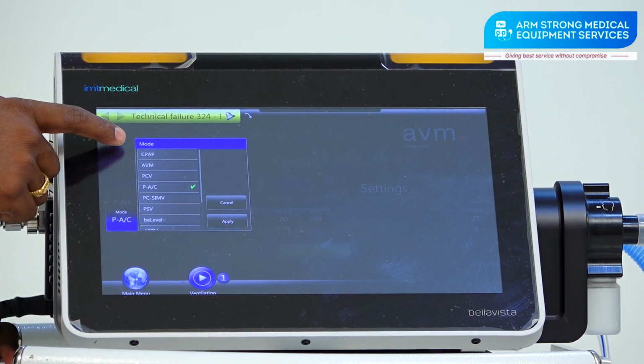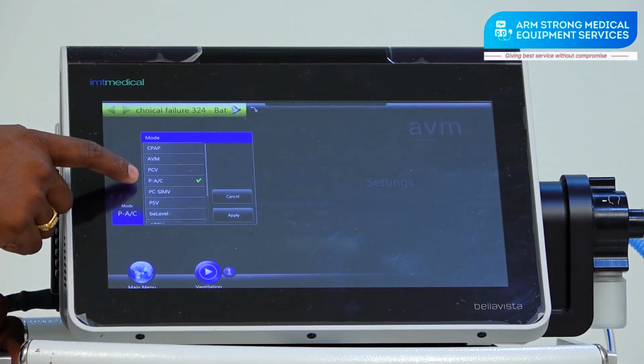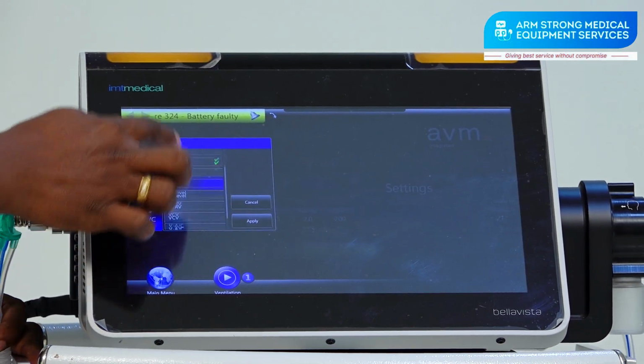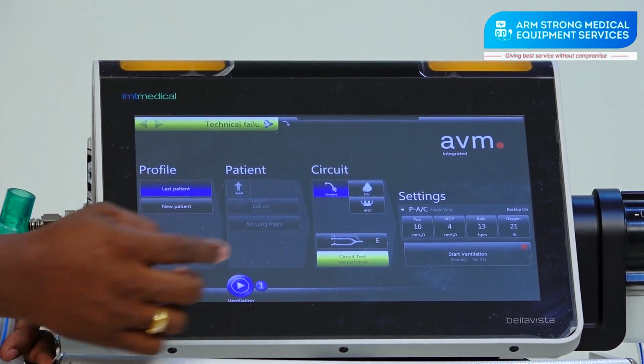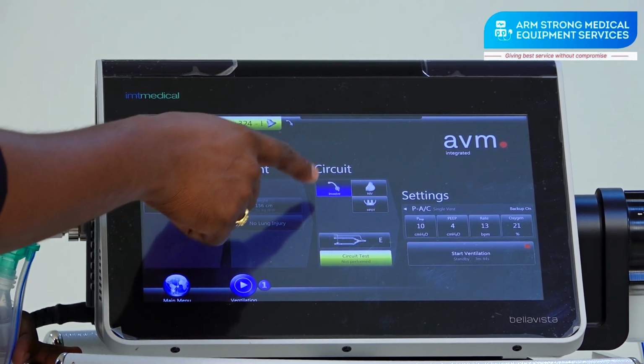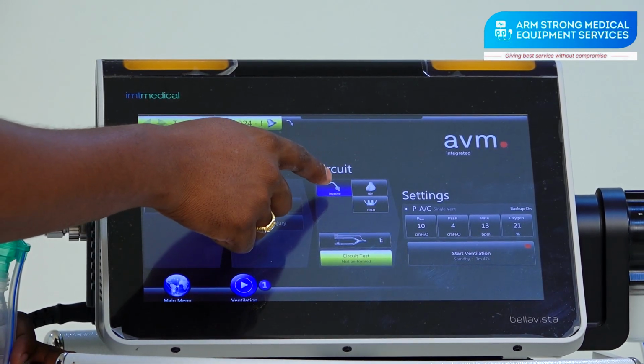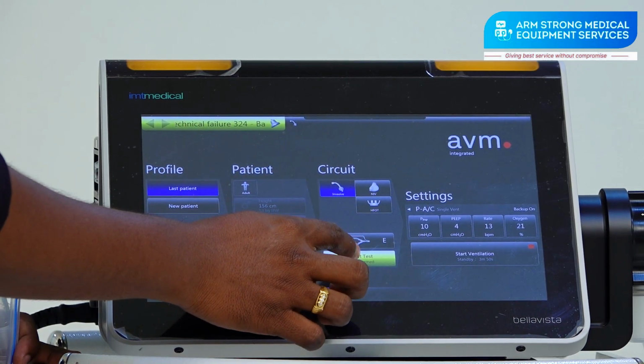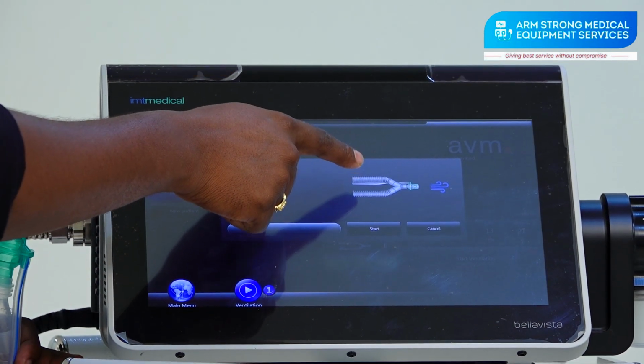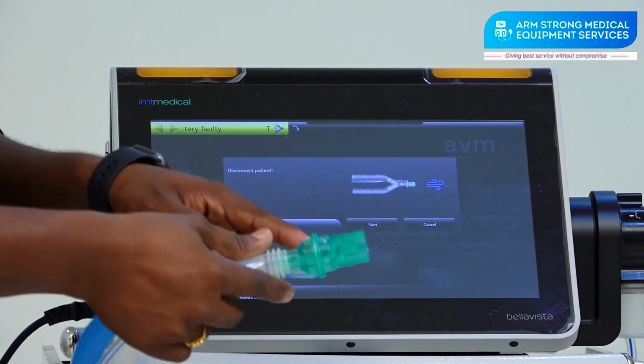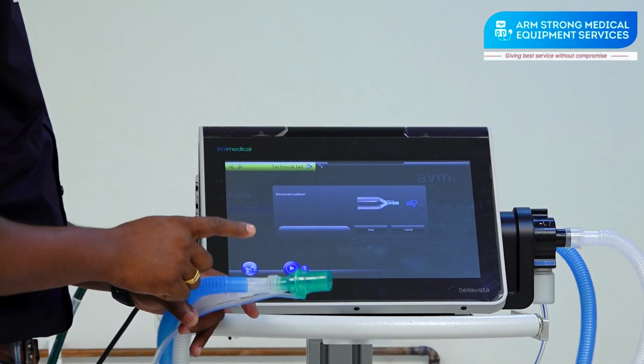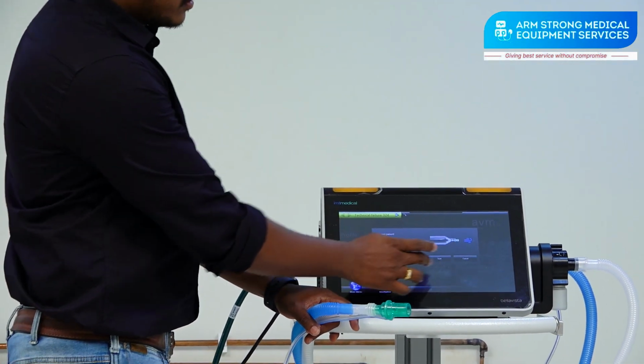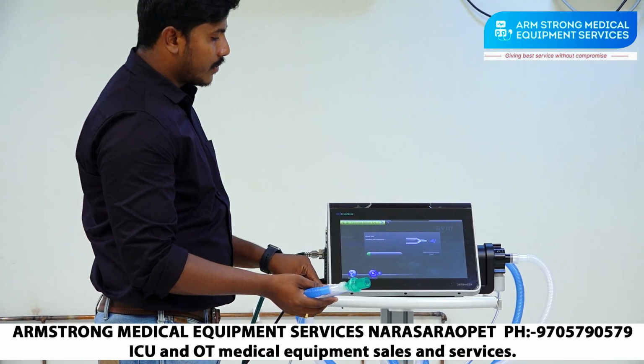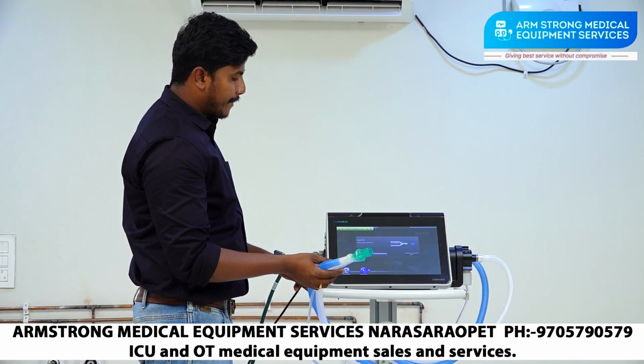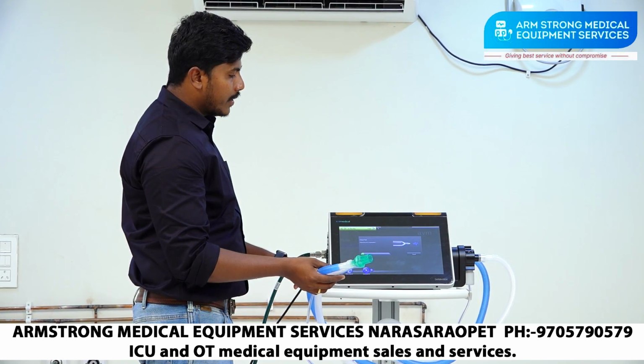See, here we have CPAP, AVM adaptive ventilation mode, PCV, PAC, PC-SIMV, PSV, B level, like that. We have all modes, APRV. So on this ventilator, first after switching it on, you can select the patient category and invasive or non-invasive, and after that we have a circuit test also. So you can do a circuit test, which checks whether any leak is there or not, and whether the flow sensor is working or not. So all these kinds of functions of the ventilator we can check on this one. So like this it will start. It will take approximately 3 minutes.